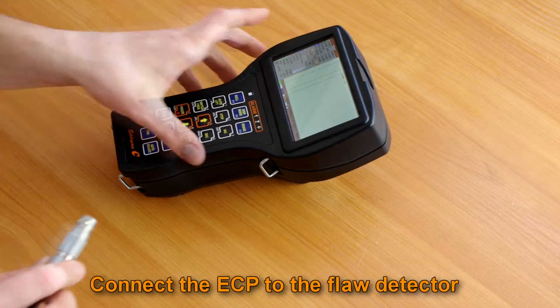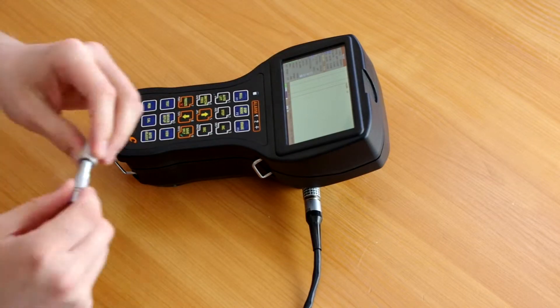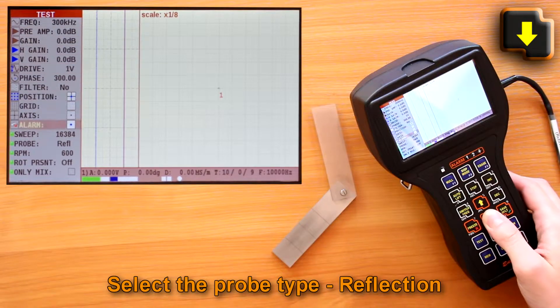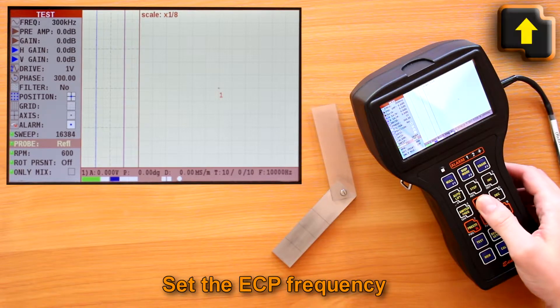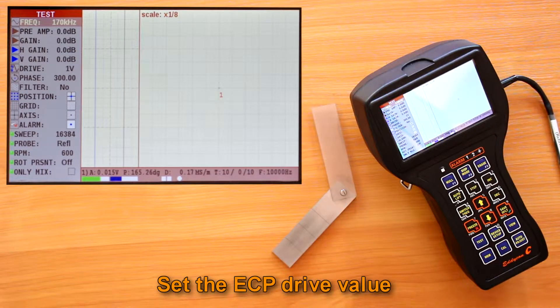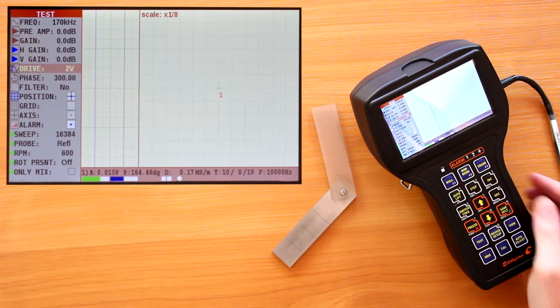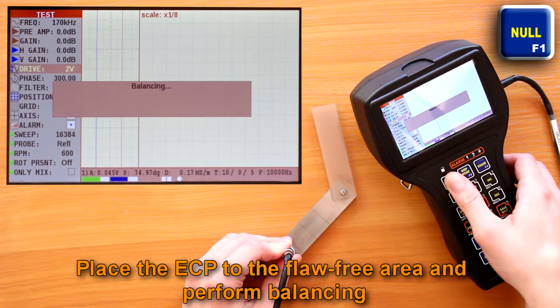Reflection probe. Connect the ECP to the flaw detector using a connecting cable. Select the probe parameter in the test menu — reflection type. Set the ECP frequency in a range specified in the registration certificate of the ECP or on the probe marking. Set the ECP drive value according to its registration certificate. Place the ECP on the flaw-free area of the calibration block and press F1 to balance the ECP.